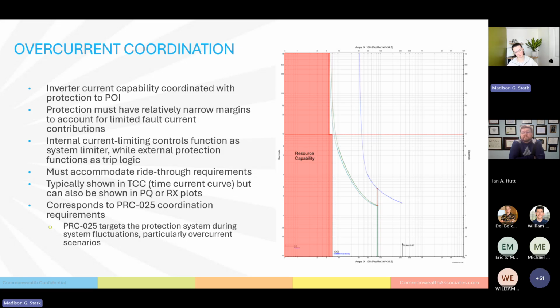So you can see this red line between these two relays. Typically, we would have a time label on that specifying that this time does include the opening time or the response time, or if you have an error margin in your CTs, like a 3 or 5% current reading margin, that also can be included in this. All of that is built into your margin when you're coordinating elements. While you don't necessarily have to put a separate curve in, you can include that in your reports or in your calculations of how you got to the required margin, not just throwing darts at a wall or picking a number out of a hat. Those calculations support or justify why the margin between your protective elements is sufficient. And on a TCC, you can show the time margin via these crosshairs, or you can show current margin here. That's another one we also show sometimes to demonstrate that level of coordination.